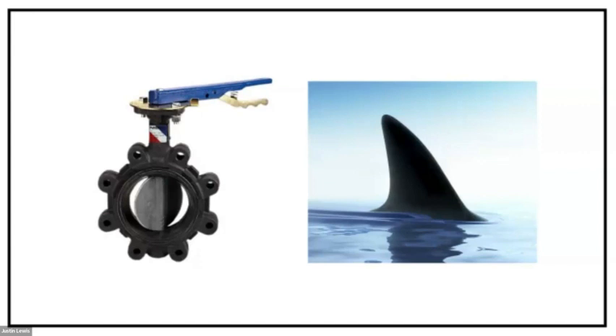Another one that's very rarely talked about is the orientation of shutoff valve blades. The orientation can dramatically affect the pressure loss to a system. This is especially important just before or after a transition or header connection. With the valve open, it needs to be oriented so that the flow of water moves past the blade like a shark fin through water. If it's oriented differently, then the water is forced to move up and over the lip and adds quite a bit of pressure. We've had some issues with headers coming off of right above a pump assembly and just killing the pump performance. And simply reorienting that valve had dramatic effects. In a full open position, the valve should have very minimal turbulence.